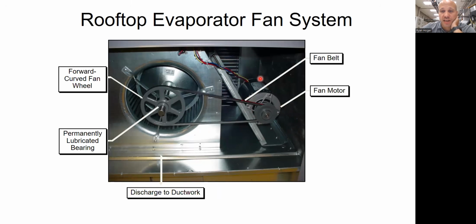What belt driven means is I have this motor here that's turning this, we'll call it a small pulley. And then there's a belt that turns a larger pulley. That is one way to get an electric motor to do more work than you otherwise would expect it to do. The other way is to take this motor and put it directly on this shaft. We'd call that a direct coupled system. It's coupled directly onto that shaft. I typically can't get as much torque that way and hence as much static pressure.